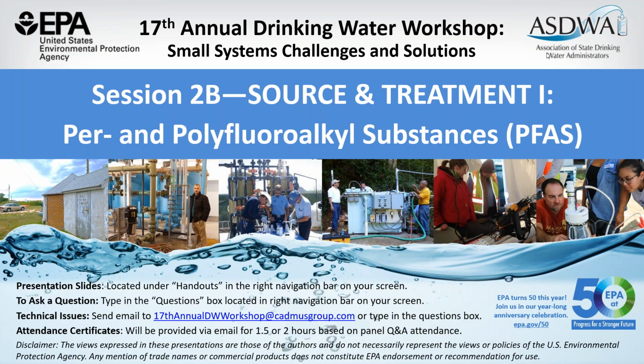On the first question, really the answer was neither. We happened to see PFBA where it was, but I think what triggered the change was contractual, or the design had a change set in at a certain period of time. We had that change at the 17-month mark. So it was really a maintenance driver. I know it sounds weird to say a maintenance driver when I also said there was no pressure drop, because there wasn't. But the decision was made more as maintenance. The design was for a change-out at 12 to 14 months or a little bit behind that. We happened to see the compounds where they were, so I think it just made sense to do it. But it wasn't that PFBA was the trigger for the change.